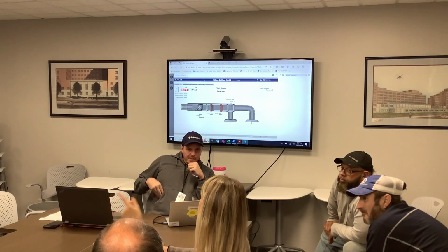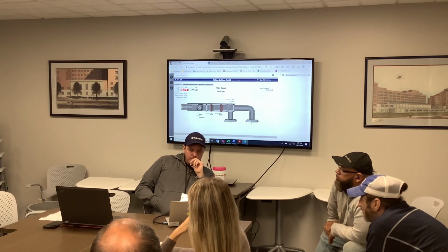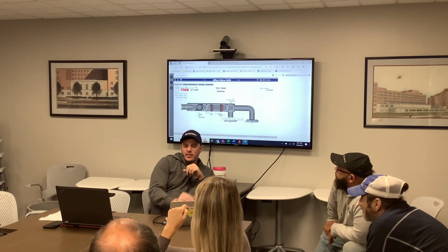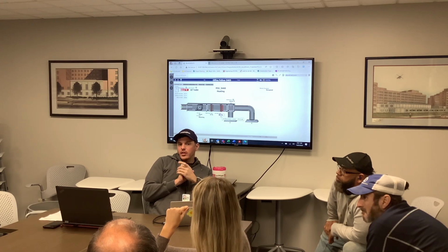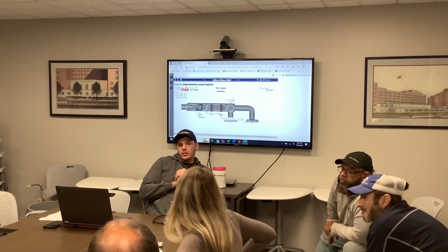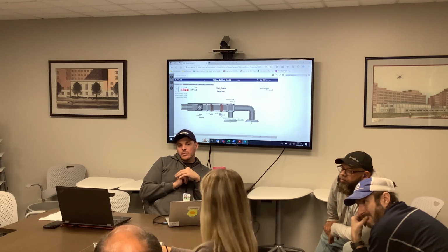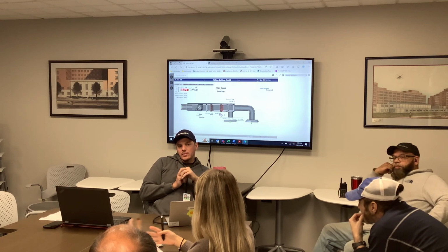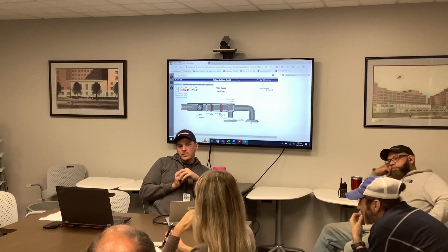So you don't have reheats, but my question would be, how do the radiators integrate with the fan coil units? So the radiators are steam, and they follow the exact same set point as this hot water valve command. So if this has a steam coil on it, that valve's 83% open, that steam valve. I understand, but with no reheat, they won't have reheats, but I'm wondering how that would, like, during that time, if it does require a reheat, how would the radiators factor in?